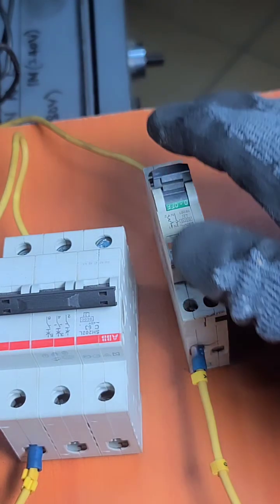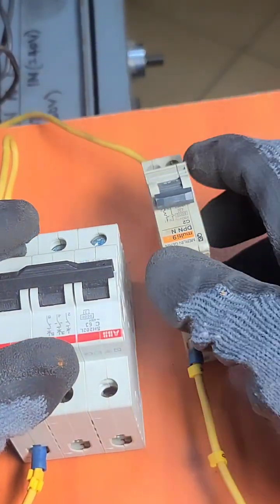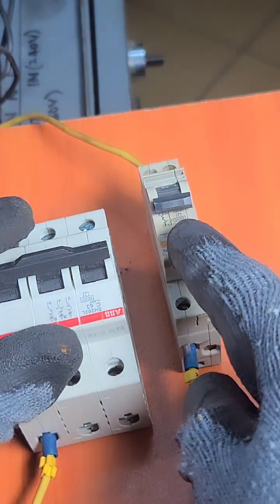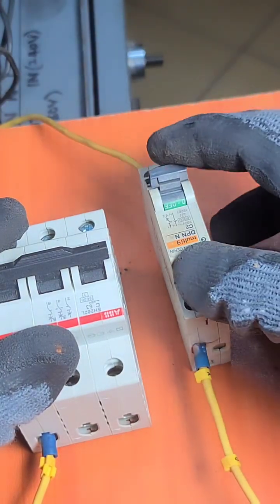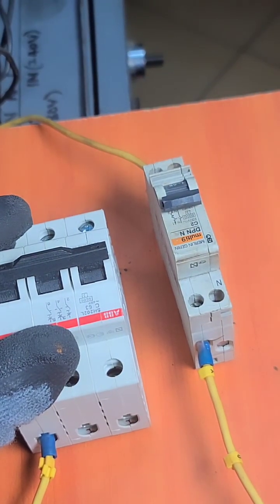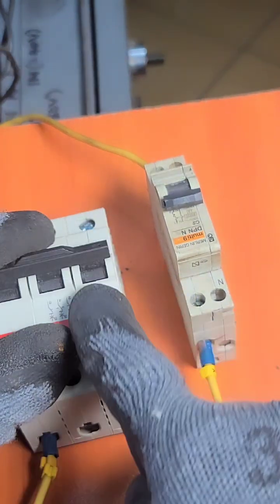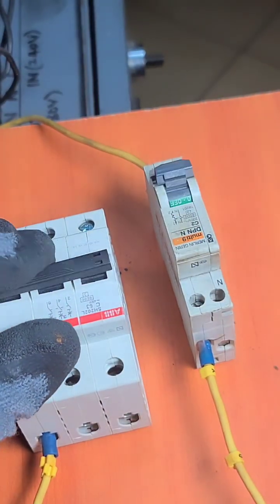So what we do now, please, before we switch on the power, we need to be sure that these breakers are off. This one is off. This one should be on, it's in the on position, so that when we introduce a short circuit on this one, it is expected that this one will flip back, opening the circuit. So we leave it on, and then we put on the power like that. We have not introduced the short circuit until we close this one. So when we close this one, it is expected that this breaker should flip to keep the circuit safe.